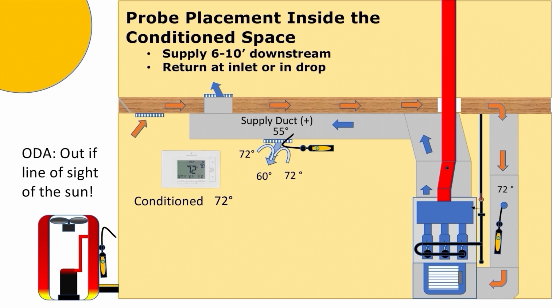So inside the conditioned space, we can be in the return air drop. So you'll notice that probe's over here in the return air drop. And then we want to be 6 to 10 feet away in the supply air duct. You want to give the air time to mix.